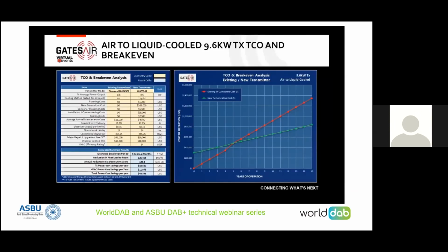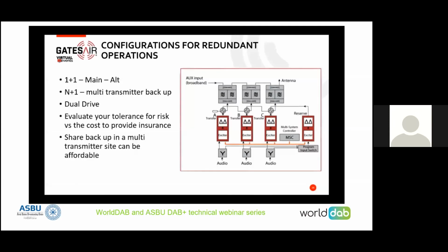Using a TCO calculator, we can compare a break-even analysis of, say, an air-cooled versus liquid-cooled transmitter, taking into account all the associated costs, the energy efficiency, and the energy consumed to evacuate the heat. For transmitters at lower power levels, typically below 1 kilowatt, air-cooled is the dominant method because liquid cooling's complexity isn't worth it when there's not much heat to extract from the building. For higher power levels, liquid cooling works quite well.